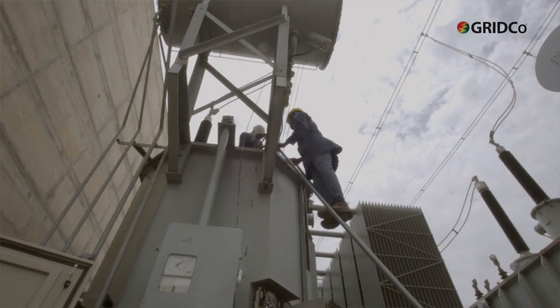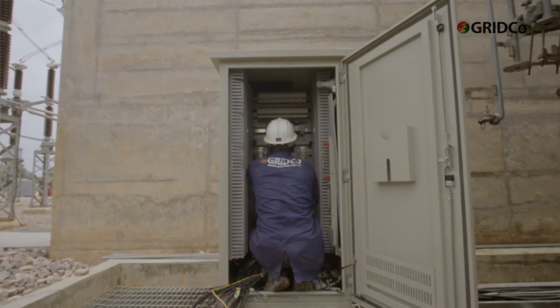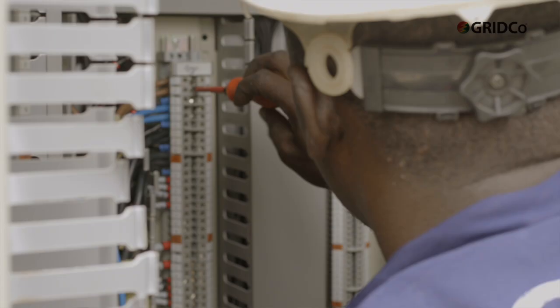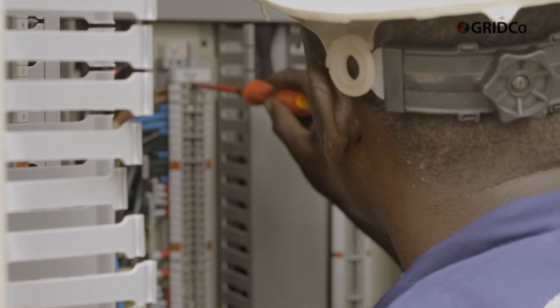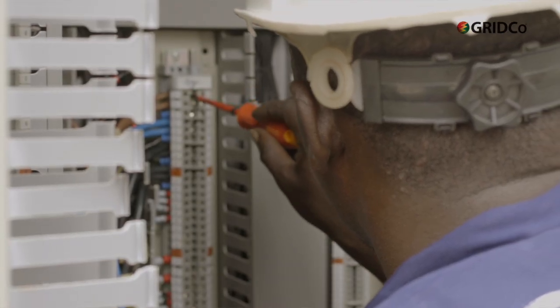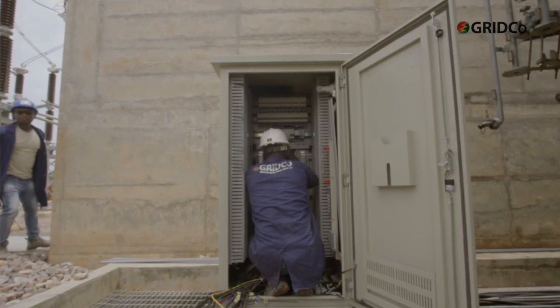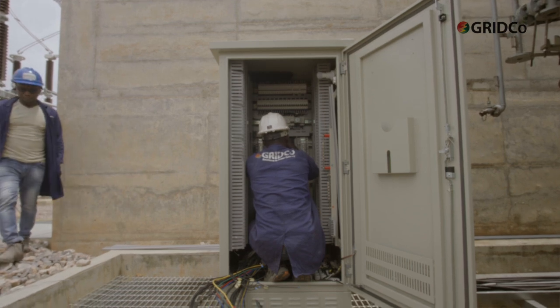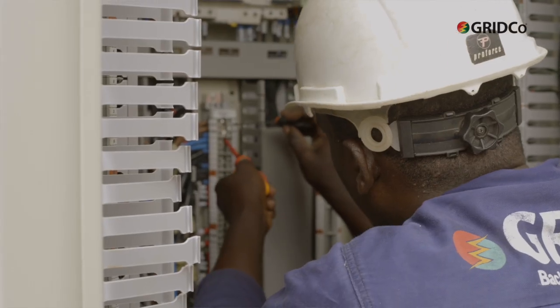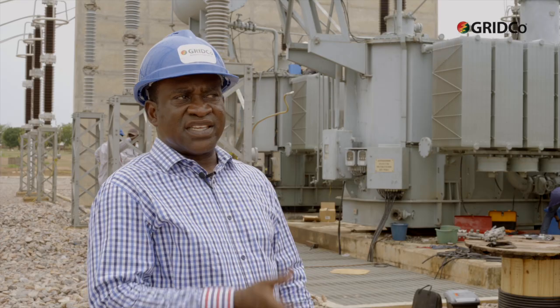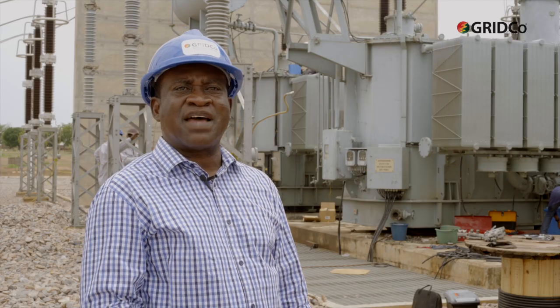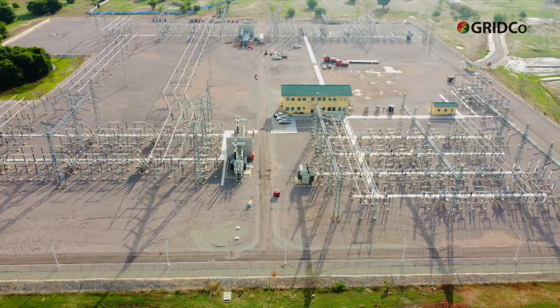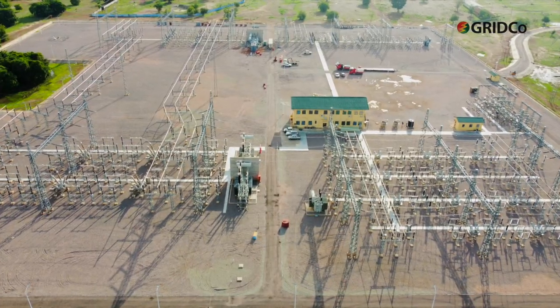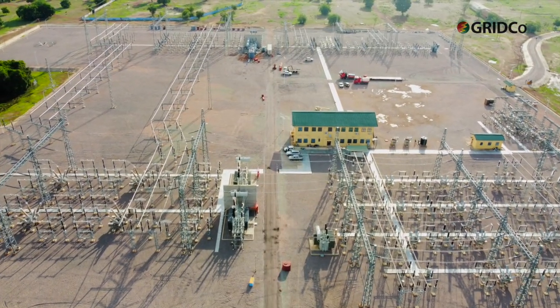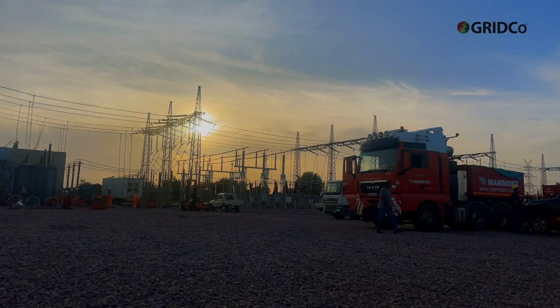What we are doing now is wiring by the protection and control section. And the work going on in that panel there is integration of the old wiring of the faulted transformer to provide protection for the new transformer that has been installed. The existing faulted transformer was a step-down transformer from 330 to 225. The new one is going to be a step-up transformer from 161 kV to 225 kV.